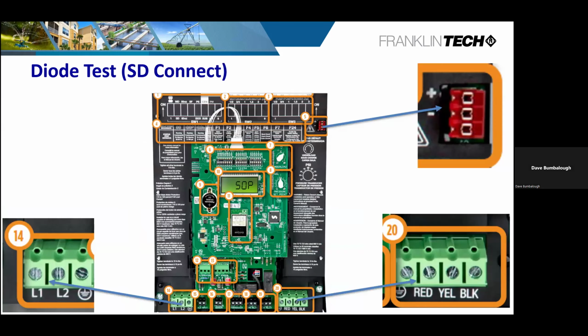So as we go through the test, I also wanted to point out the smaller drives typically have that same ability to check for input on the diode test by identifying the DC bus connection. It's usually protected by a little cap. That cap will be identified as a plus and minus as well. And you're going to do the same test. For the positive, you're going to put your black lead into that connection, and then you're going to go down and test L1, L2. You're going to check also your motor lead side, which will be, in this case, the red, yellow, black, which is going to your motor. So what you're looking for, again, is somewhere between 0.2 and about 0.5. If you see OL or you see 0, that means something is happening internally inside that controller, and it will identify whether it's on the input side or the output side or both. So the smaller stuff can be identified as well.